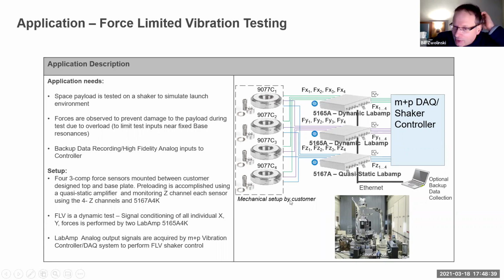So there's no need to necessarily have those closed form expressions at hand. What's more important is that the M+P shaker has the geometry of the sensors and the vibration fixture, and it automatically handles the calculations. That's more or less what goes on nowadays, though not always, since it depends on the sophistication of your system and controller. Some folks don't have that sophistication yet—it's sometimes a budget issue—but eventually that does happen over time.